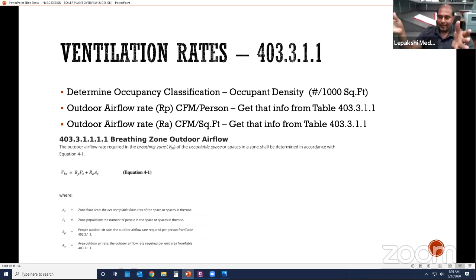Mechanical code 403 states how much air is required per hour—this is called air changes per hour, covering how much total air and how much fresh air is required. You can get this information from tables, and it depends on the class of application. For instance, a classroom requires certain air changes every 6 hours, providing 300 CFM. So there are standards you pick and choose depending on your design.